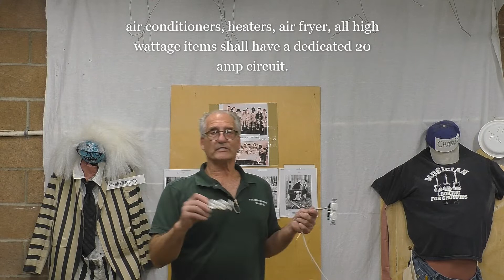The solving of the problem is right now - put a sticker on the box. This product needs a dedicated 20 amp circuit on its own individual circuit with nothing else on it. That's the only thing that's going to solve it. Because the arc fault breaker, I don't know what it does, but it won't solve that problem.